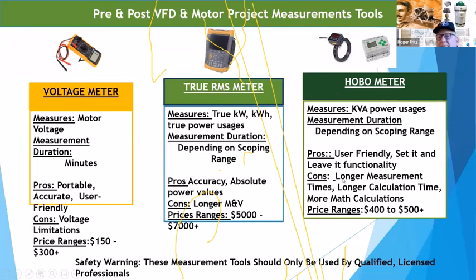These are what they call HOBO meters that you put in to look at things over time. They come with current transformers, and they connect in. What they do is record over time so that you can look at the real operating cycle and load cycles of those pumps and applications. You just stick those in the cabinet. They're fairly small, leave them in there and take a look at it. That's the fold-out, it's a trifold form. The book also has the calculations for pump horsepower, GPM, your pressure, your volumes. Very useful tool.